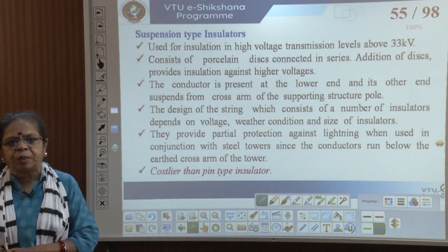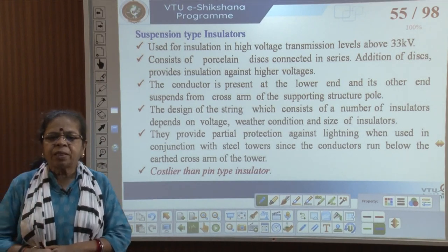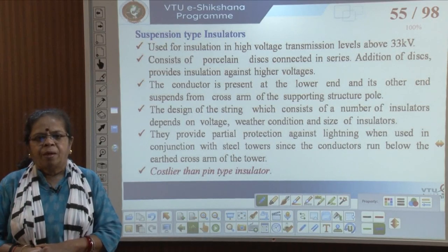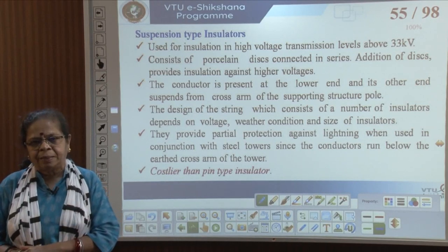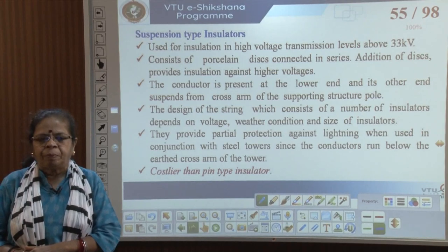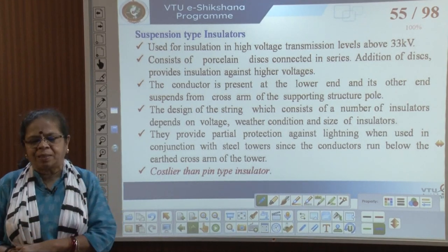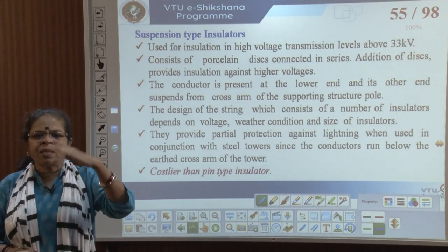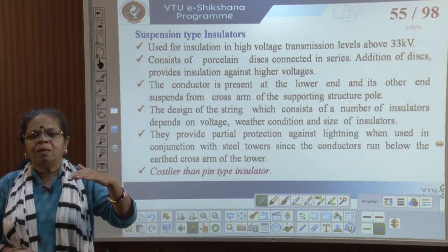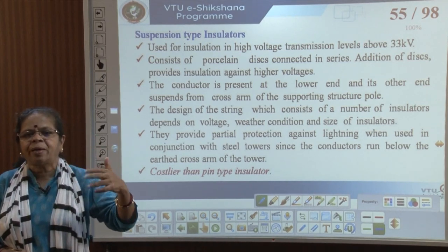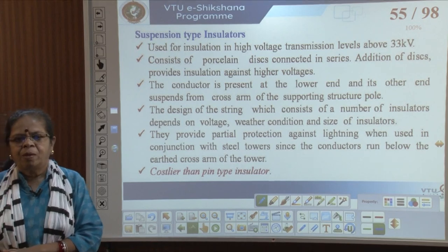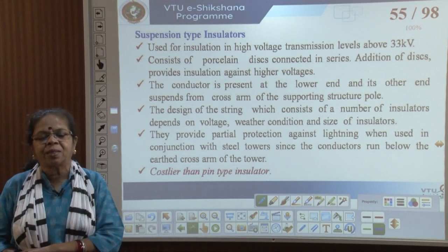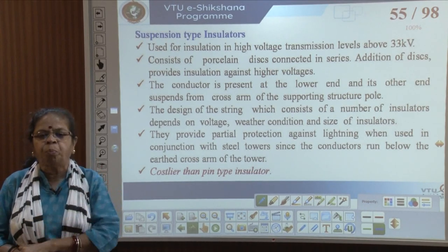Suspension type insulators are used for voltages above 33 kV. They consist of a number of discs connected in series. As you add more discs, insulation is provided against higher voltages. The conductor is present at the lower end and the other end is suspended from the cross arm on the pole.